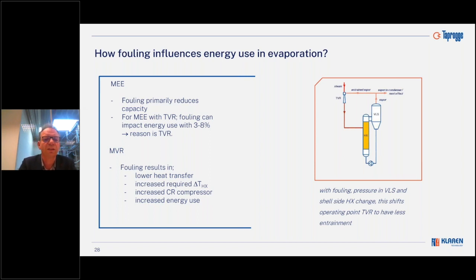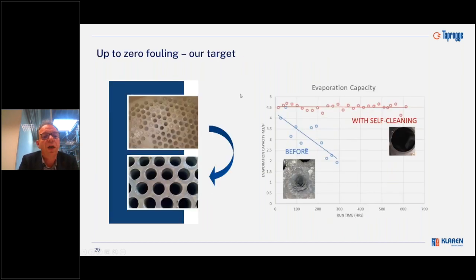But in an MVR, it's even more direct. Because if fouling reduces your heat transfer, that means that your blower will need to do more compression ratio to maintain the same capacity. That means the delta T over the heat exchanger has to increase. And this automatically, one-on-one, increases the compression ratio of your compressor. And as we have seen in the previous slide, if this compression ratio goes up, your electrical consumption goes up. So there's a direct relation between fouling and the performance of the MVR in terms of the use of electrical energy. So fouling has a significant influence on energy efficiency, but also on the performance in general of your thermal system, because it also influences your capacity and your uptime.